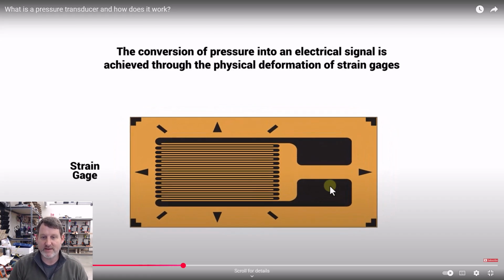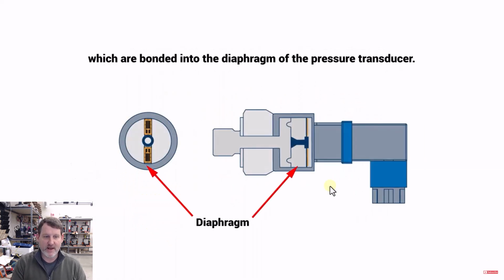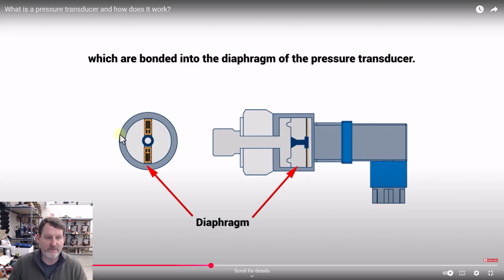To use these in a pressure transducer, they're actually seated inside of the transducer. It's just kind of a front-on view looking at it kind of in that direction. Inside here there's this diaphragm, and then there's these 2 strain gauges on either side. And this dark blue circle is this sort of plunger here. So, and here's the diaphragm. So the water can flow in here and it's like a flexible rubber diaphragm. As pressure increases here, it pushes that diaphragm to the right here, which pushes the plunger to the right, which stretches and bends these two devices here, which changes the voltage going through them, which is really kind of cool.